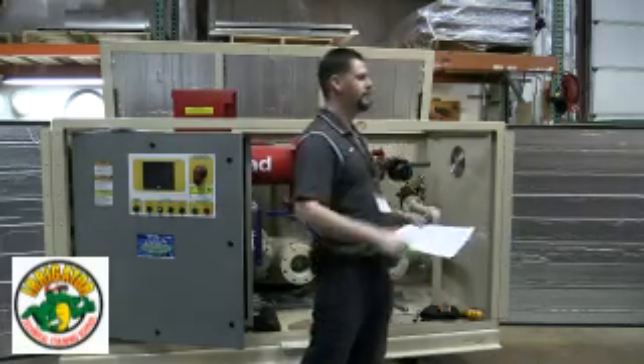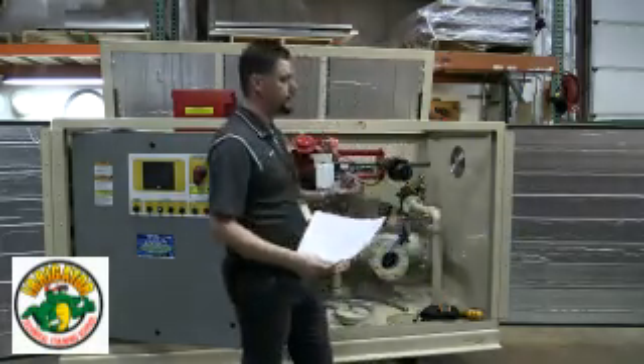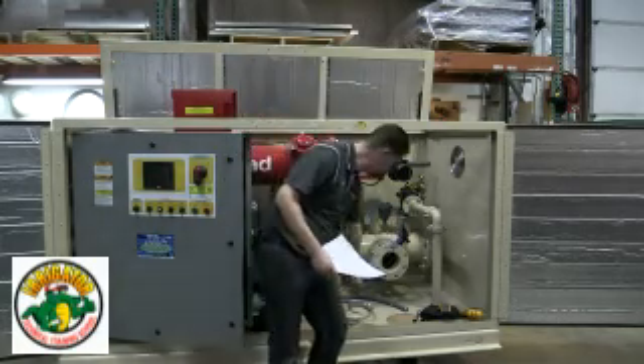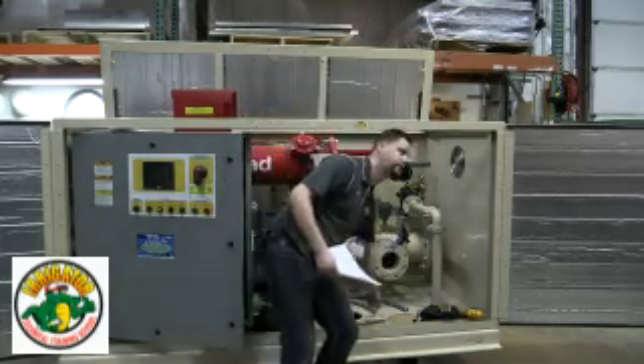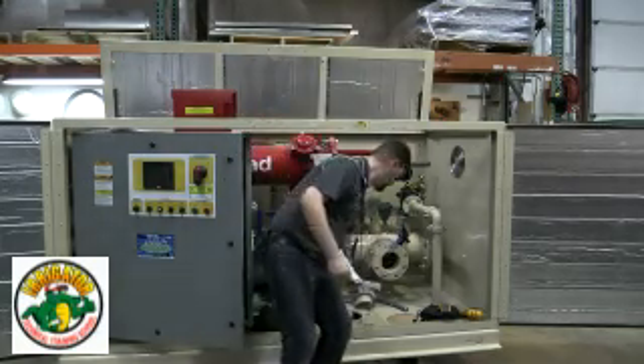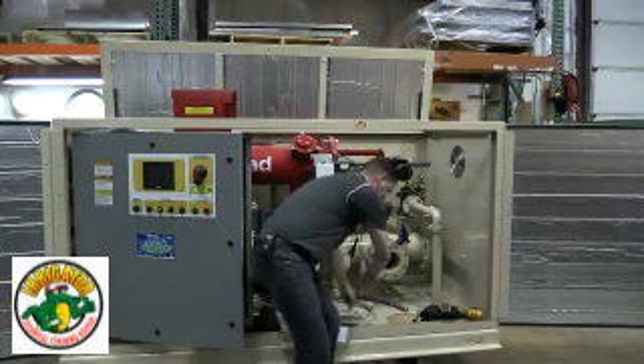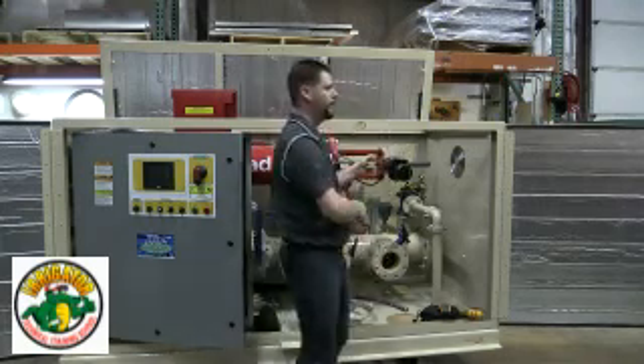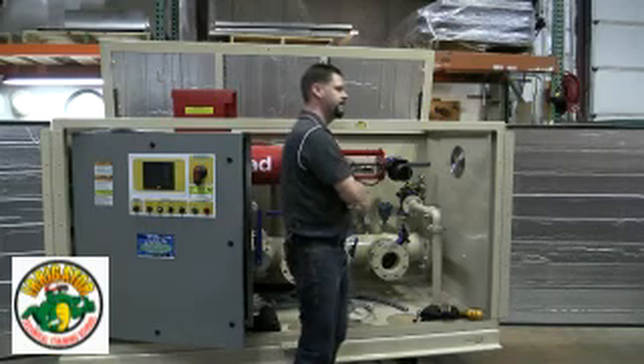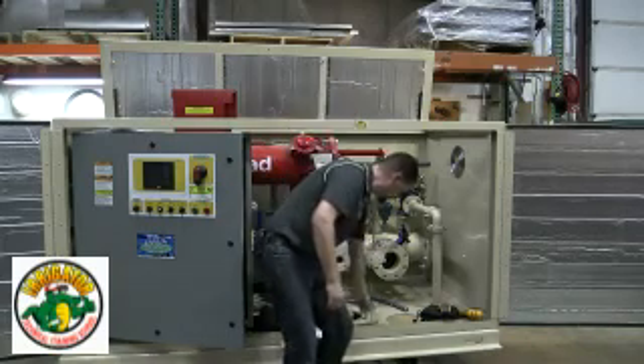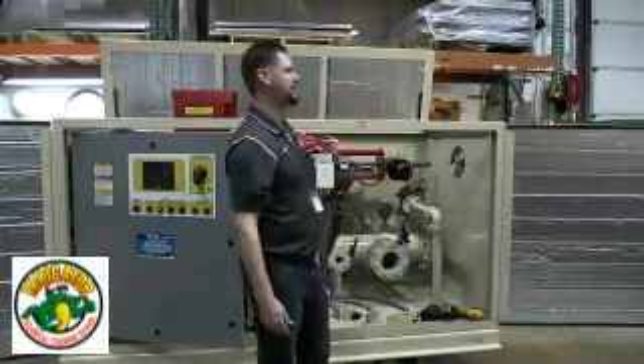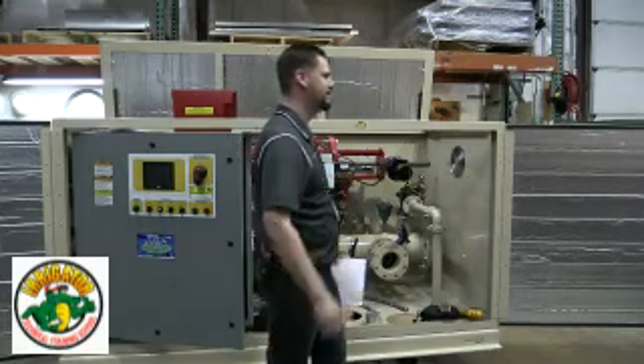Okay. So in auto, we want to pull the low water float. This is an imaginary low water float. Grab that cable. Pump stops. Perfect. Throw it back in. Pump restarts. Auto restart. Also tested.